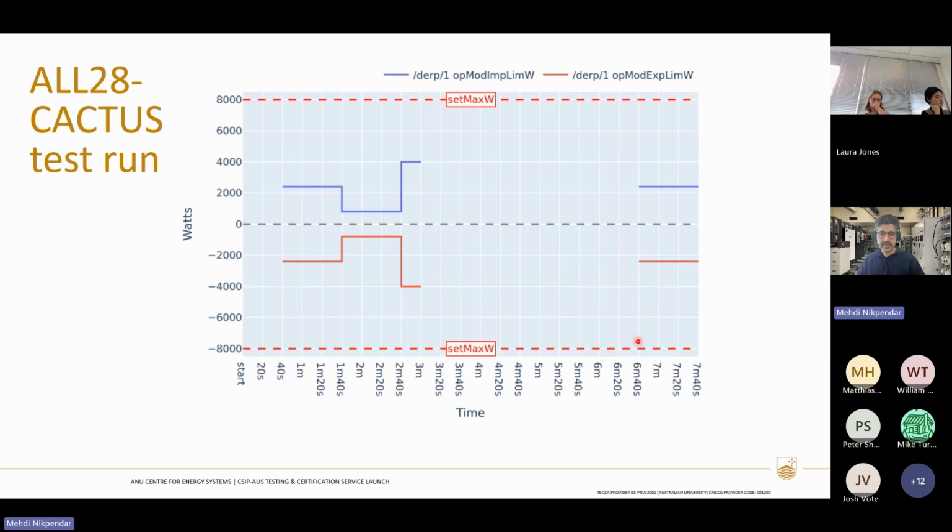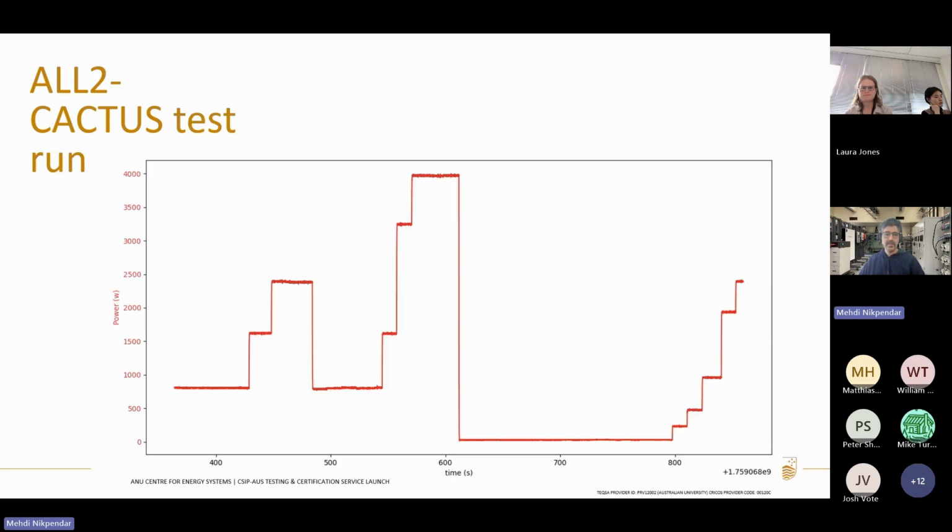And this is part of the reports. Mike just talked about how this is an interesting one, to be able to monitor the DER commands or DER controls as they are sent by the server. And we will validate the DER behavior by capturing the power. So we have power meters in our lab that can log the data as we run the test event, and that's what's used for this test.